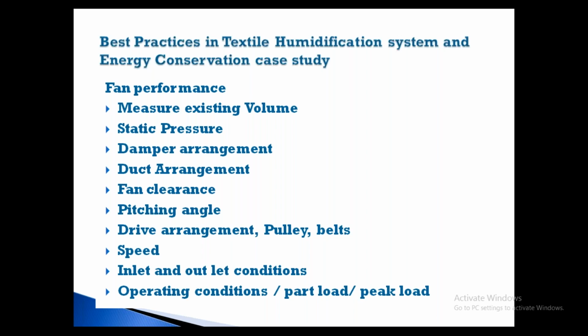So in the fan, based on your flow and your static pressure, power will play a role. Free air delivery means there will be lesser power, because mostly we have to try to attain the free air flow after the fan. So it is a closed system. We always have to check how the outlet is given after the fan.